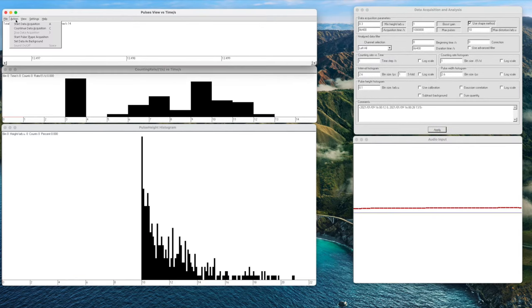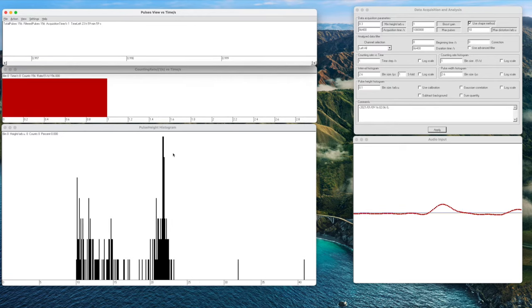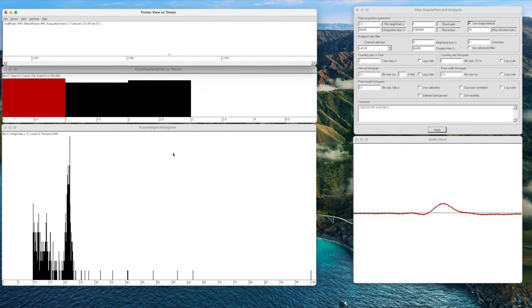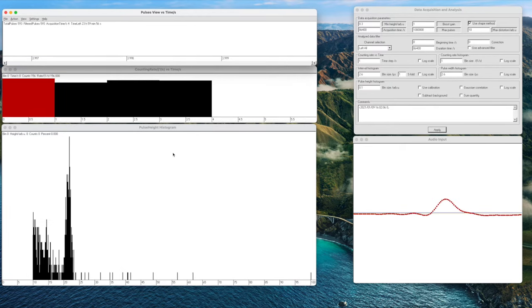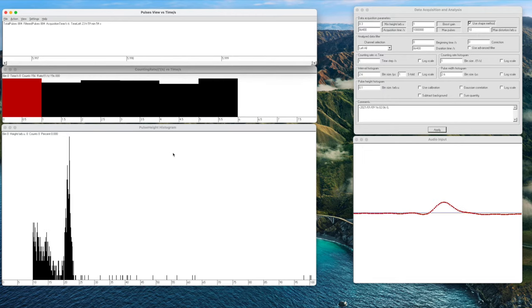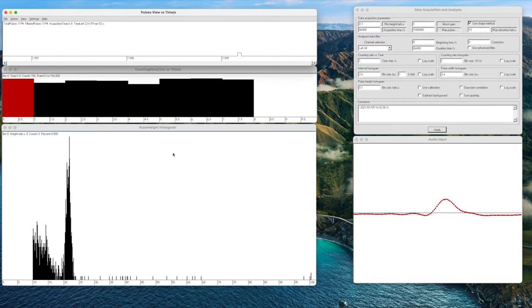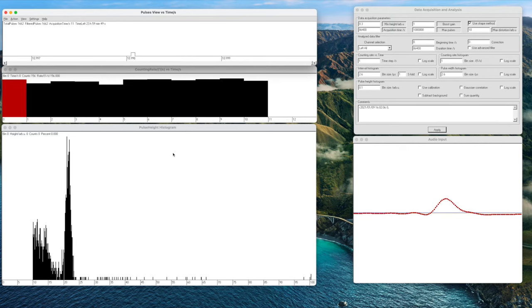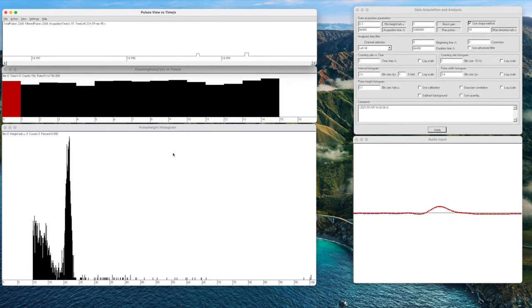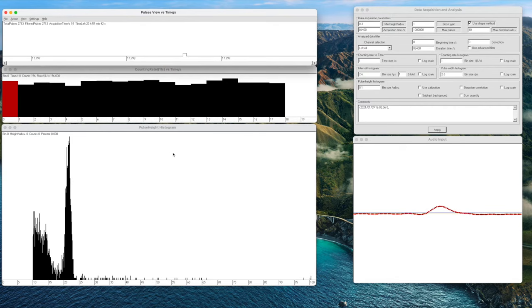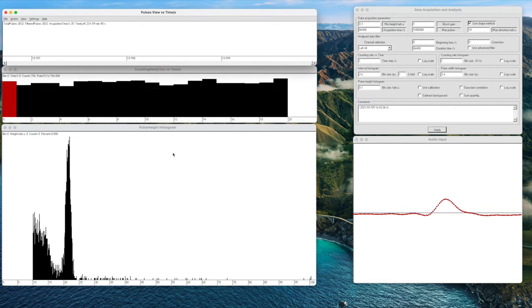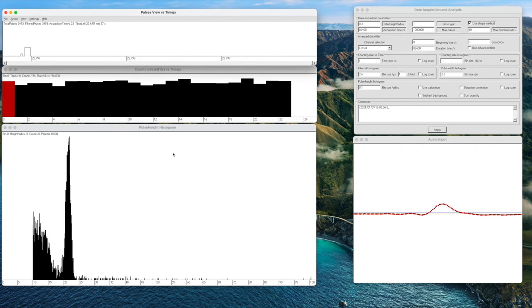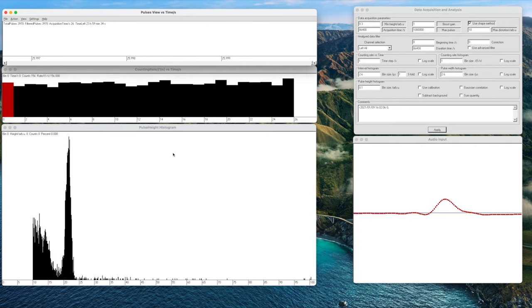So we go to action, start pulse shape acquisition. Now PRA is collecting a large number of pulses and looking at the mean pulse shape. There is a mathematical calculation that the software does here which is explained in more detail when you download the PRA software. There is a very comprehensive manual where Mark explains this method in detail but it is too complex to go through in this particular video.